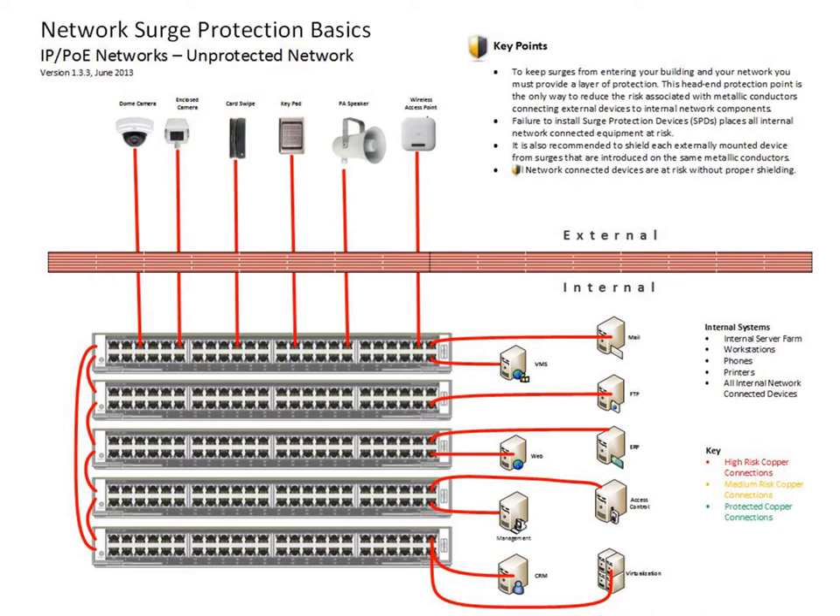This diagram is meant to illustrate the different devices that may be located outside of the building that are physically interconnected with internal systems on the same network infrastructure. Examples include IP cameras, access control card swipes and keypads, PA speakers, and wireless access points. Some key points to note: to keep surges from entering your building and your network, you must provide a layer of protection. This head-end protection point is the only way to reduce the risk associated with metallic conductors connecting external devices to internal network components. Failure to install surge protection devices places all internal network-connected equipment at risk.